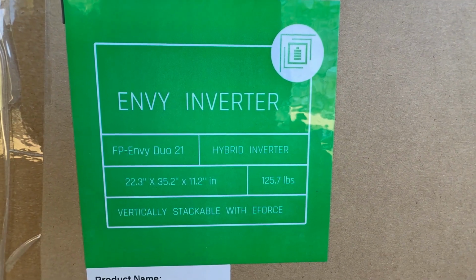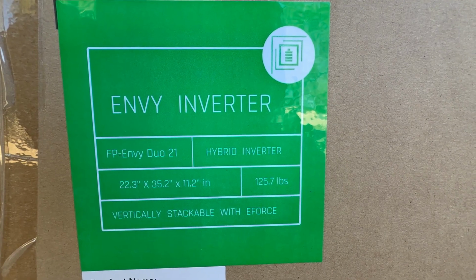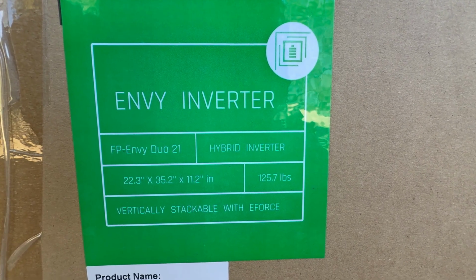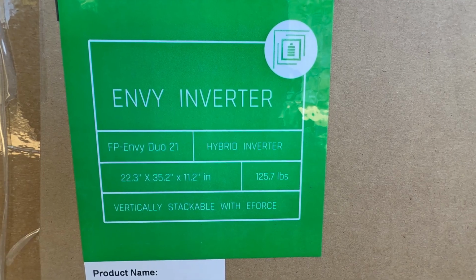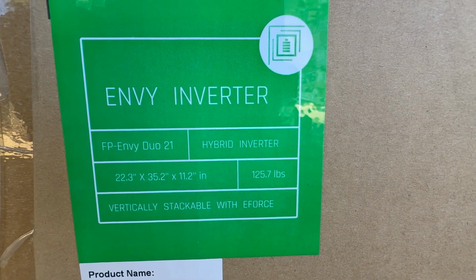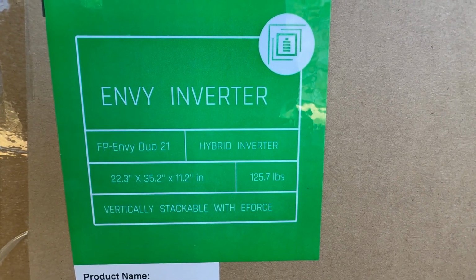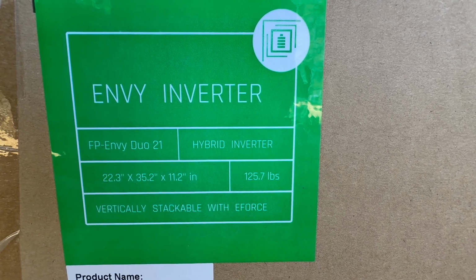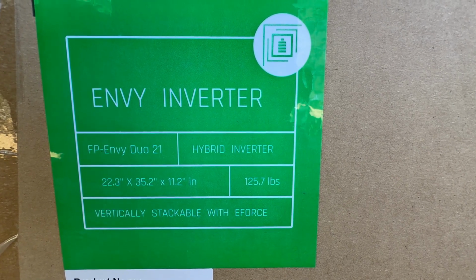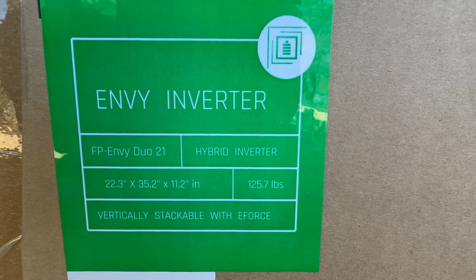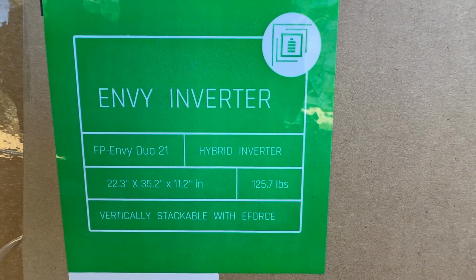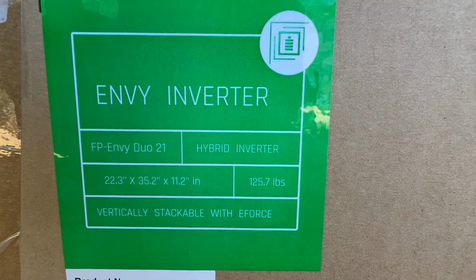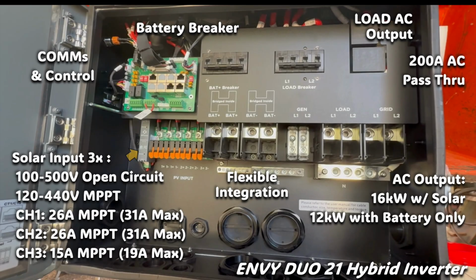The label on the box confirms most of my measurements. Width of 22.3 inches, height of 35.2 inches, depth of 11.2 inches, and the weight 125.7 pounds. So, I'm going to try to use all the machines I can to move this one into place. Let's go around and look at the features inside the Envy Duo 21 inverter.